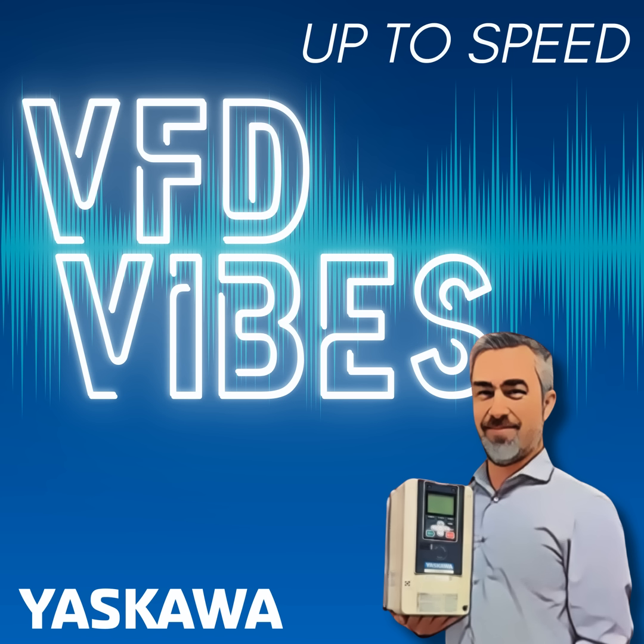The other new technology that's available is matrix technology. Full disclosure, I am the product manager for the Yaskawa U1000 matrix drive. This drive is an AC to AC drive. It's the one model on the market that produces a variable frequency, variable voltage output to a motor from an AC power source without the use of a DC bus for power conversion.